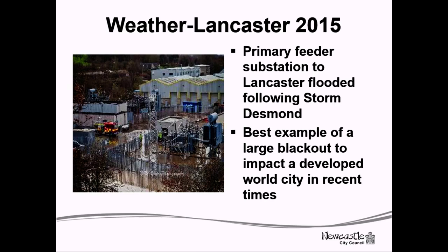The decision was vindicated because the power station, the substation, then flooded. As a result, Lancaster was cut off, the river level receded, and an effort was made to reconfigure it. They managed to get it back up for 30 minutes, but then the bus bar, the central point in the substation that fed the city, collapsed due to water ingress, and Lancaster was cut off for about 2 to 3 days. As I said, it's the best example of a large blackout to impact a developed city in recent times, and some of the lessons will be elucidated later.